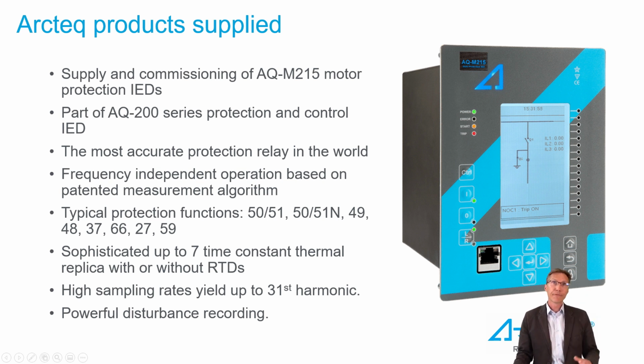A quick look at the different products supplied in the project. Starting from the motor protection IEDs, type AQ-M215. This is part of the AQ200 series protection and control IEDs, which are the most accurate protection relays in the world. For the motor protection, the frequency independent operation based on the patented measurement algorithm can be quite interesting, especially in case of frequency drives or soft starters in use. In this case, we had direct started motors.